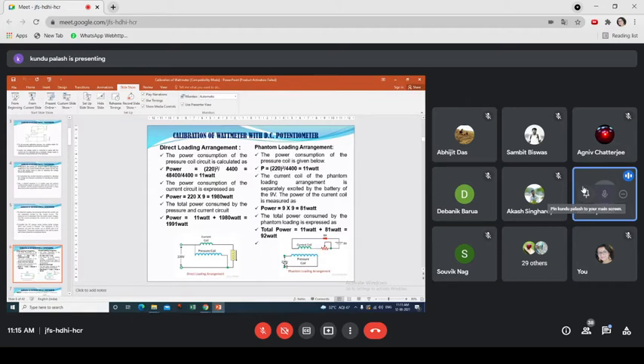In a phantom loading circuit, two potential sources are required. But in an actual loading circuit, where the wattmeter is actually put into the AC or DC circuit, it is called the normal loading circuit or physical loading. So what is the advantage of phantom loading? In physical loading, the total power drawn from the potential source is the sum of the power consumed by the load plus the power wasted across the current coil circuit due to the resistance of the current coil, however small, and the power lost in the pressure coil circuit.